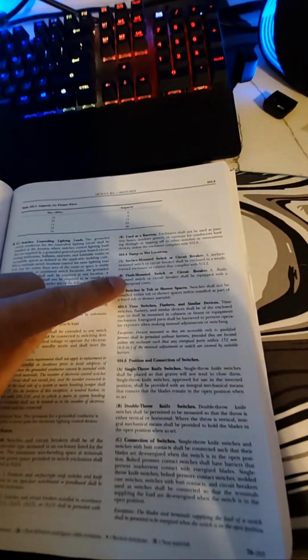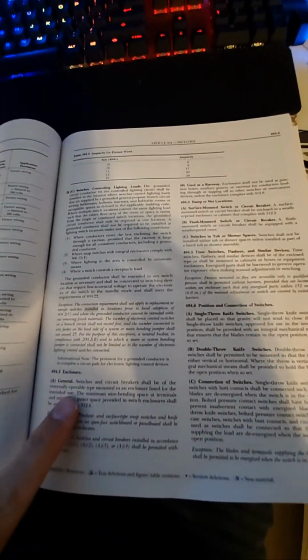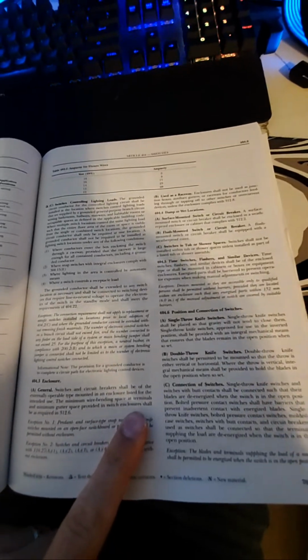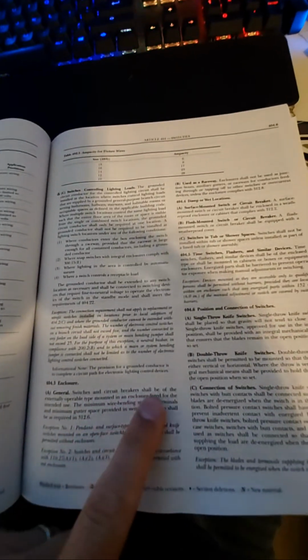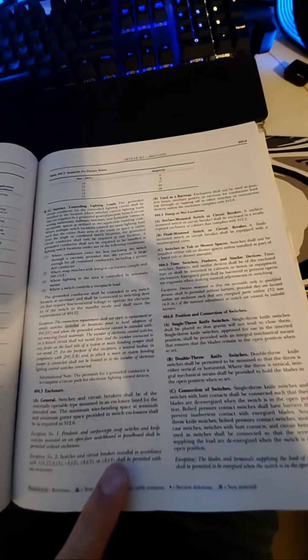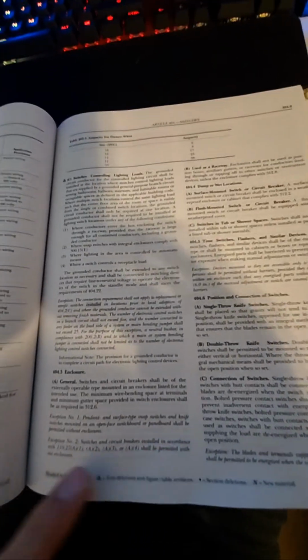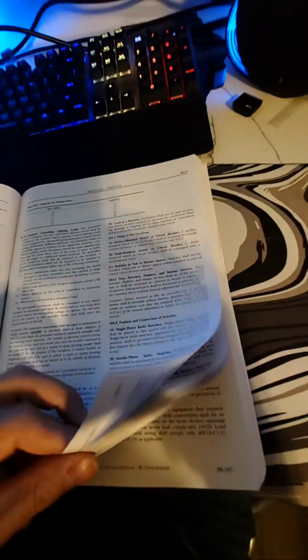Here's 404. There's the scope. We're looking for location. Here's enclosures there. That's where you're mounting the switches. That's actually pretty close. Switches and circuit breakers shall be of the externally operated type mounted in an enclosure listed for the intended use. That's pretty close. But this is where it says switches and circuit breakers installed in accordance with. So we're getting pretty close to where to find them. So we're going to keep going.